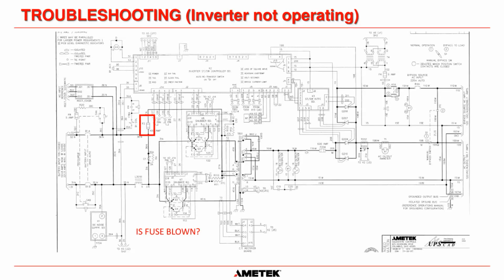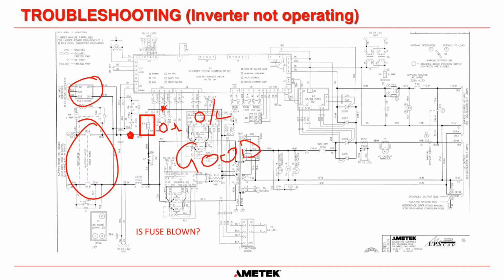But if you want to be safe and you want to turn off the charger, turn off the battery, then you can go in with your Fluke on resistance, and you can measure between that point there and that point there. And if you measure round about 0 ohms, the fuse is good. And if you measure OL on your Fluke, then the fuse is bad.